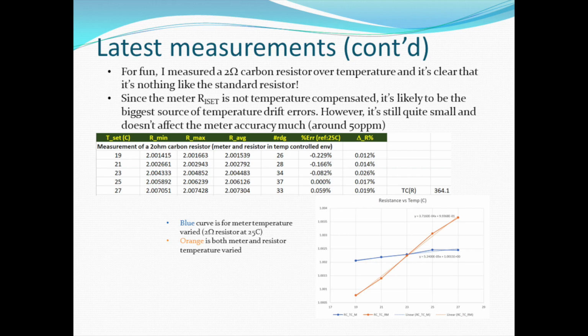the same range. There's a slight difference from the previous measurement. You can see it is slightly positive. I'm not exactly sure why, but I think it could be that my temperature setting may not be as good because I don't have a very well controlled environment for that. But it's still roughly less than 50 ppm or so, which I think is acceptable. And overall, I think the meter should be doing fine over this type of temperature range.